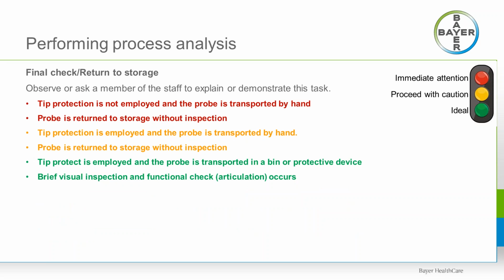So finally, we want to observe what happens after disinfection. Again, how is the probe transported? Is tip protection in use? Is a bin being used? Is the probe just dropped off, or does someone check the probe prior to placing it into storage? Ideally the probe is transported in a bin using protection, and before being returned to storage, someone takes a final look at the probe.